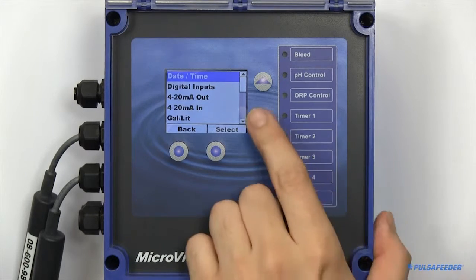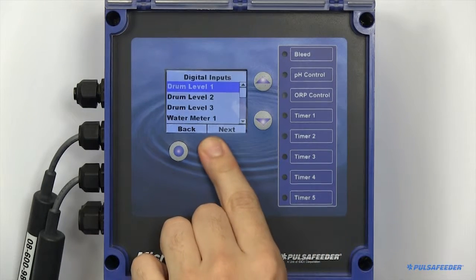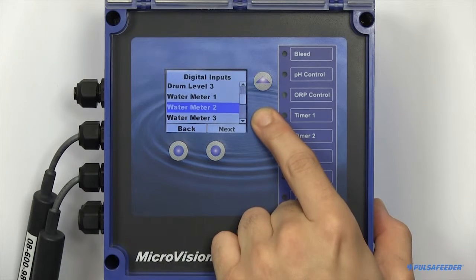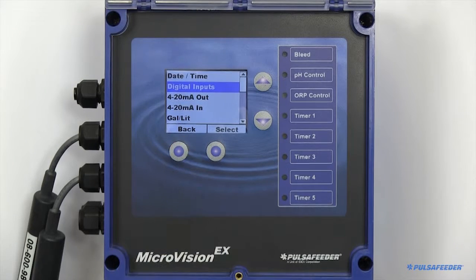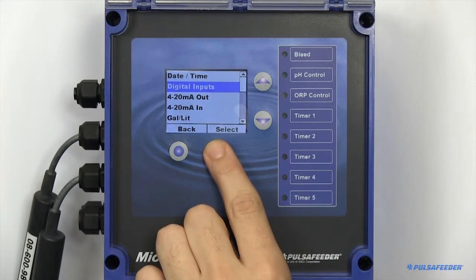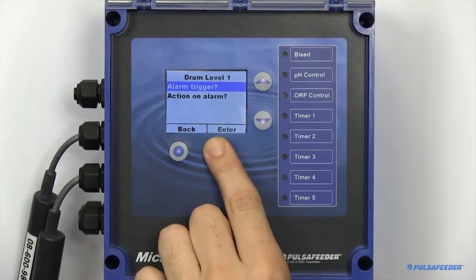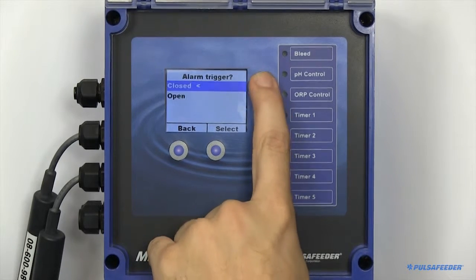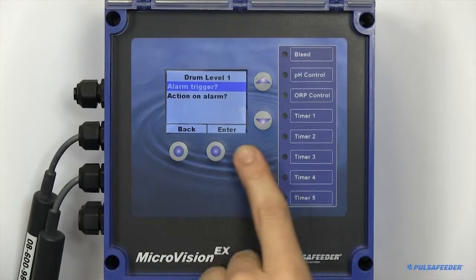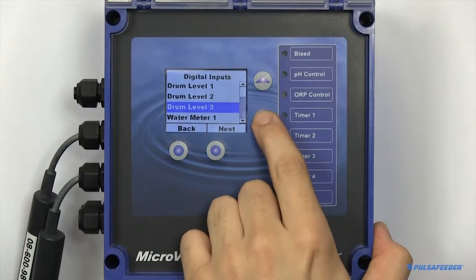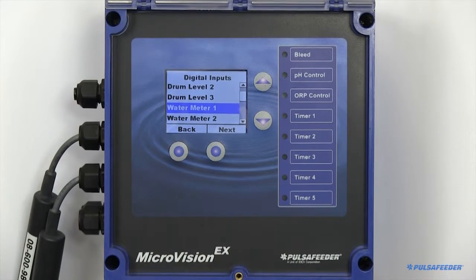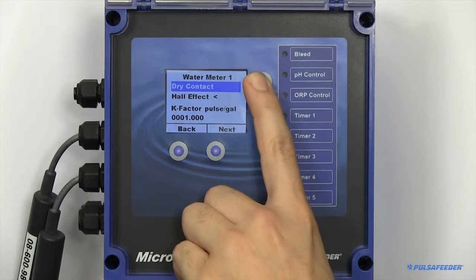The digital input screen is where you can set your drum level sensors and set up your water meters. Drum level sensors can either be configured to open or closed logic and alarms can also be configured dynamically. Water meters can either be set up as a dry contact type or a Hall effect water meter. Each have their own independent multiplier.